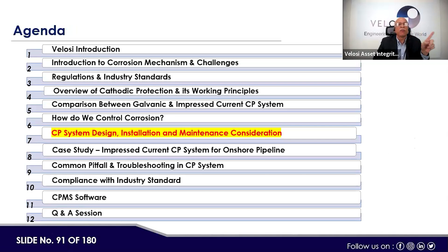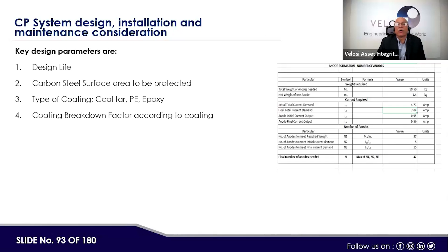Consider the design life of the asset, a carbon steel pipeline to be protected, coating type such as coal tar or FBE epoxy, then the coating breakdown factor according to the coating used, then exposed metal surface area at coating defects. Then soil resistivity, soil analysis covering sulfide, carbonates, chlorides, and pH — important to assess the degree of corrosiveness externally. Electrical isolation, and foreign structures like earthing or pipeline crossings need to be considered. Then protection criteria: minimum -850 millivolts and 100 millivolt shift. Then current density requirements, in milliamperes per square meter.